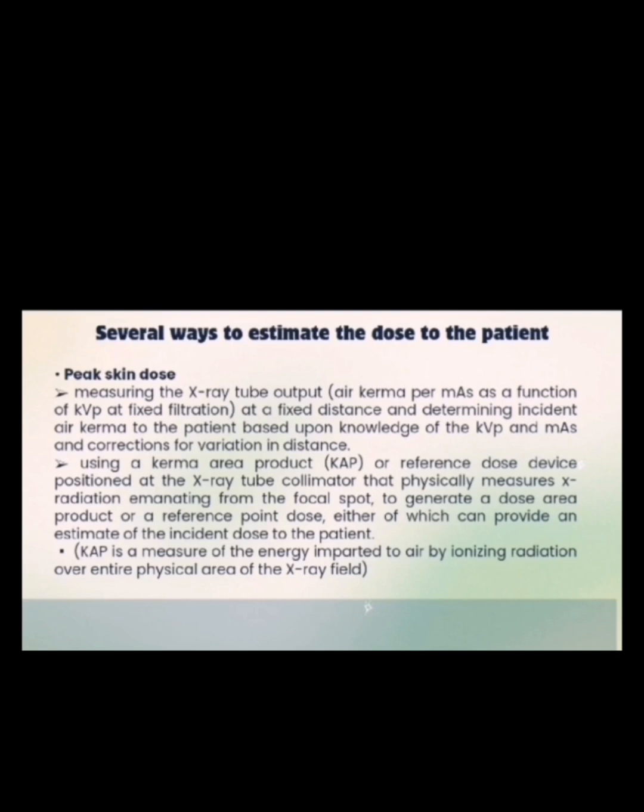But what is KAP? KAP is a measure of the energy imparted to air by ionizing radiation over the entire physical area of the X-ray field. And also, it is the appropriate measurement for total radiation incident on the patient's skin and is an indication of the total amount of radiation imparted during the examination.